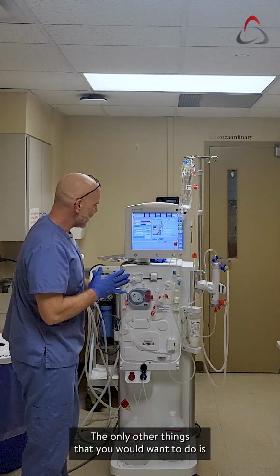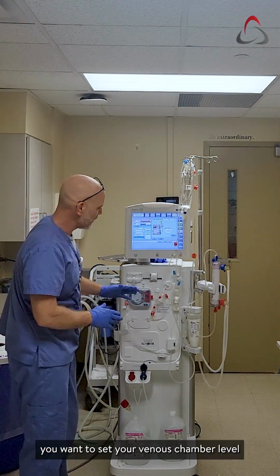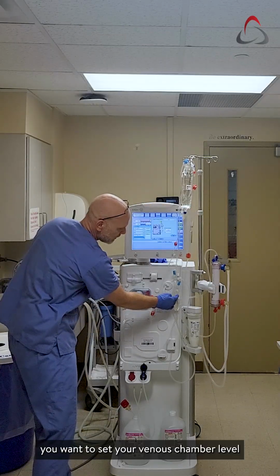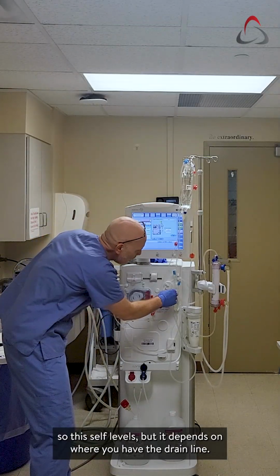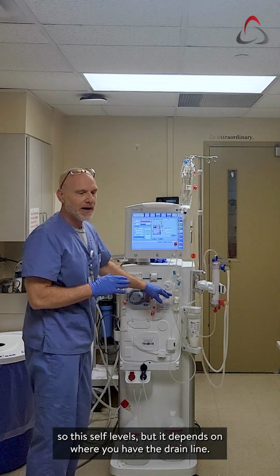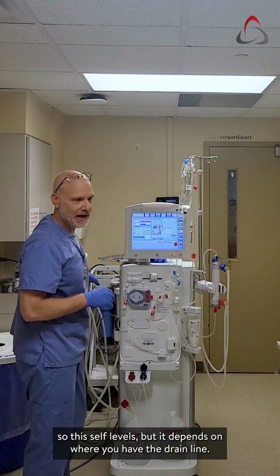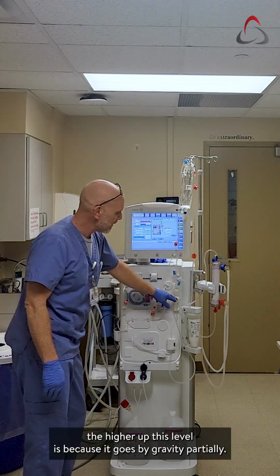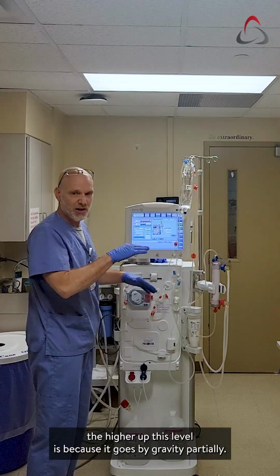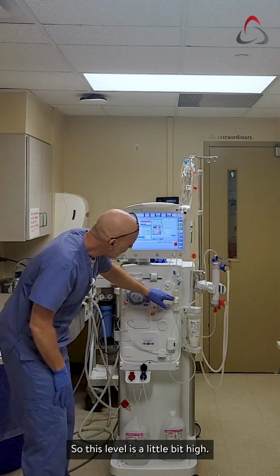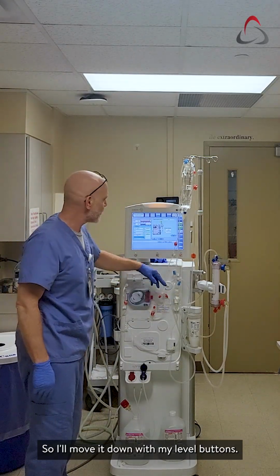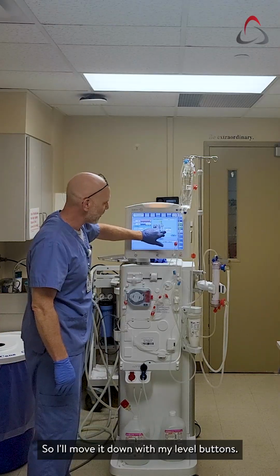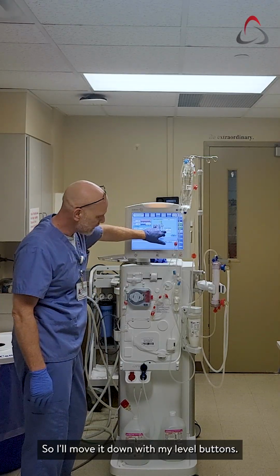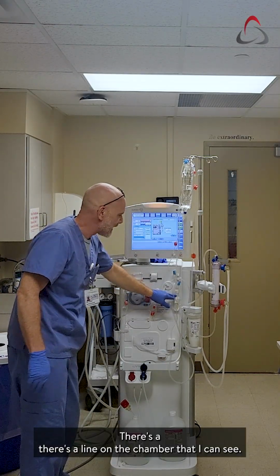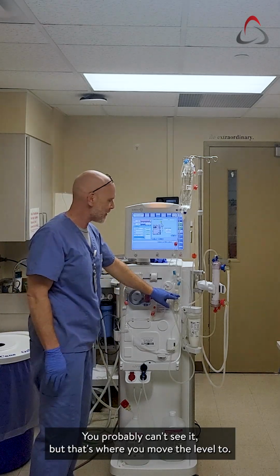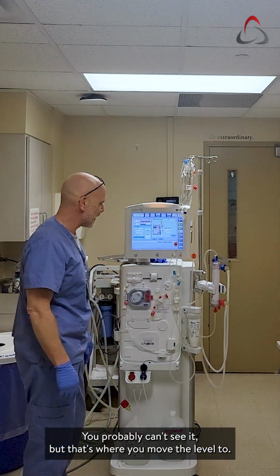The only other things that you would want to do is you want to set your venous chamber level. So this self-levels, but it depends on where you have the drain line. The higher up you have the drain line, the higher up this level is, because it goes by gravity partially. So this level is a little bit high, so I'll move it down with my level buttons. There's a line on the chamber that I can see. You probably can't see it, but that's where you move the level to.